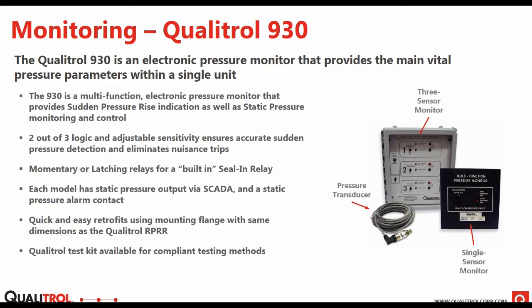And along with just doing sudden pressure indication, it also has static pressure indication, so constant tank pressure over 4 to 20 that can come out. And then it also has the built-in seal-in relay function. So it kind of brings everything into one and gives you more information with a more accurate sudden pressure indication. And then we have a similar test kit available for this, just like the rapid pressure rise relay, but for this monitor.